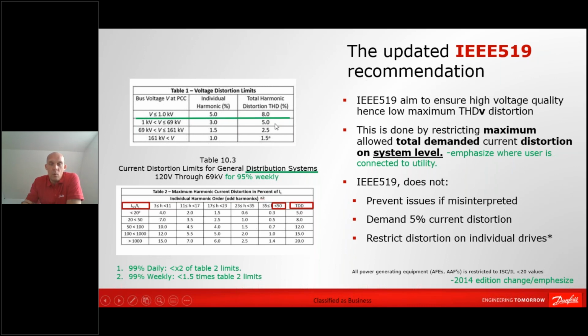IEEE has one overall goal, and that is to reduce the voltage distortion. So the overall goal of IEEE, you can see here on the left-hand side, is that you should avoid the voltage distortion on your power supply being more than 8%, or 5% for the individual order. This 5 and 8% was added to the standard as part of the updates. Before that it was 3 and 5%, so now we allow a little more distortion on the power grid compared to what we had before.